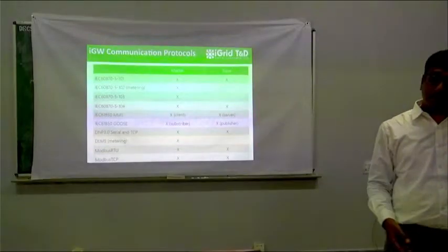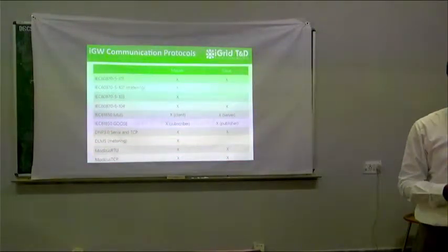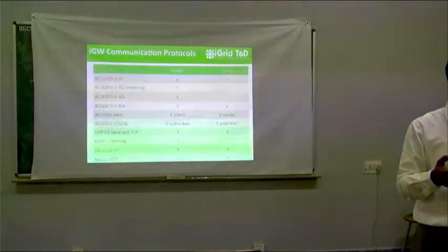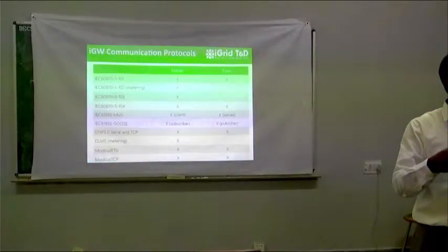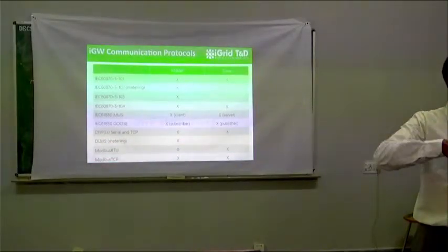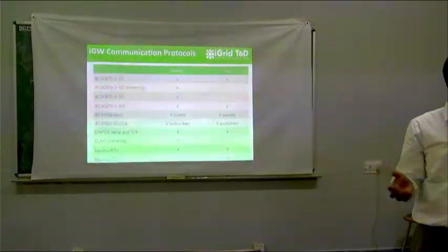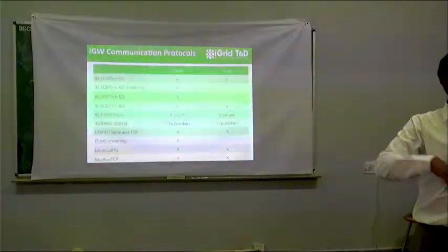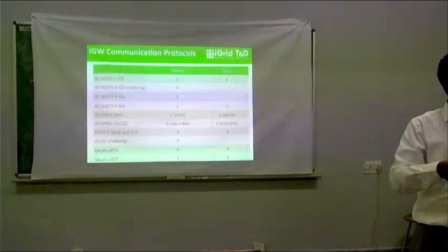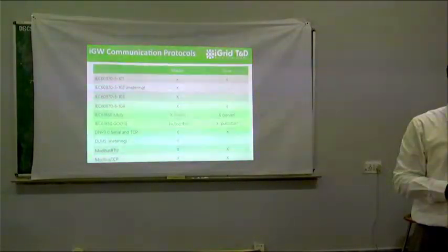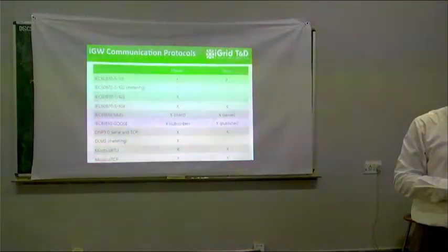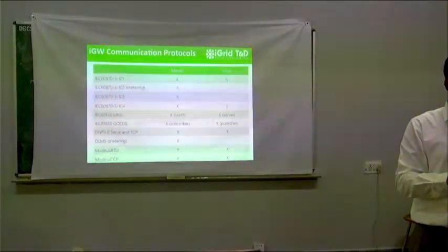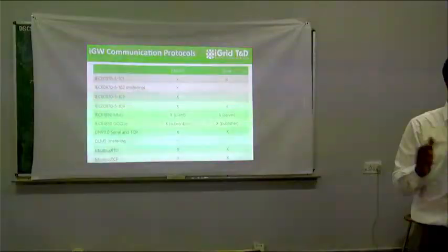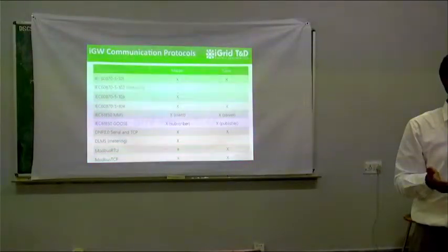If I communicate on 61850, we have what is called an ICD file. I need to give an ICD file so that the data can be read by the person reading from my gateway. So I create an ICD file and give it to the customer, and the customer will read it in their SCADA. So to that level, it supports all the protocols, and based on customer requirement, we take licenses of different protocols.